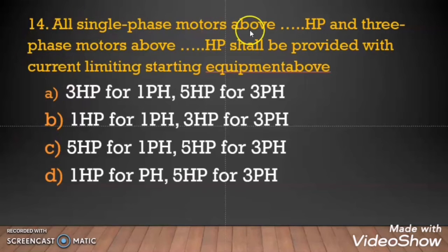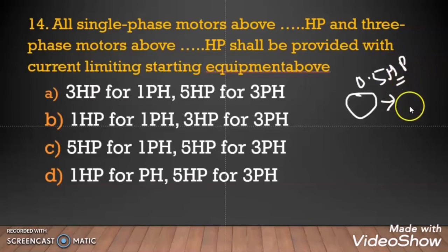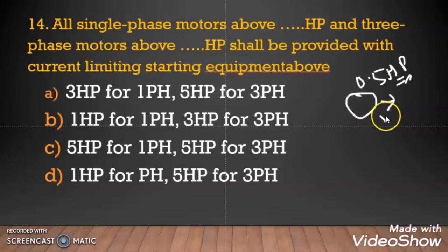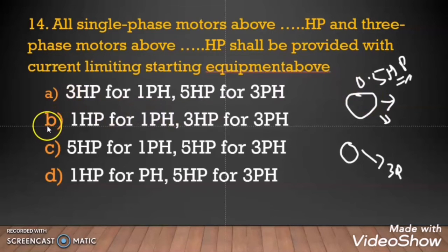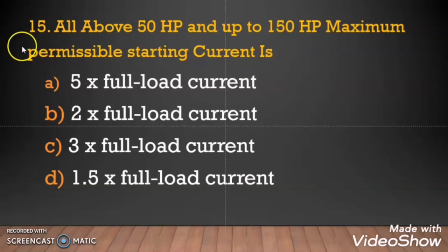Question 14: All single phase motors above how many HP and three phase motors above how many HP shall be provided with current limiting starting equipment? All induction motors take high inrush current at starting. The answer is: for single phase, 1 HP motor and above requires a starting mechanism, and for three phase, 3 HP motor and above requires a starting mechanism such as star-delta starter, VFD, soft starter, or DOL starter.